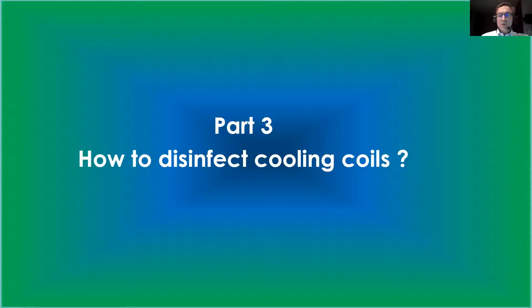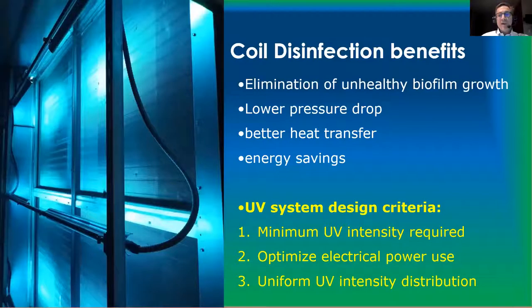So therefore, we don't have to put a ton of UV watts on the coil. For air, it would be very different. For air, it's moving and it's moving fast. We only have half a second to do the job. For a cooling coil, we typically have an hour. And I'll explain why an hour later on.